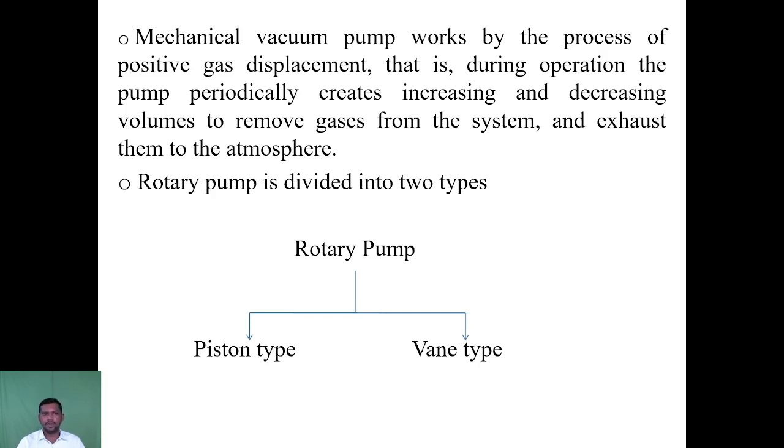So it works by the process of positive gas displacement. During its operation, the pump periodically creates increasing and decreasing volumes to remove gases from the system, and exhausts them to the atmosphere. This is the working process.